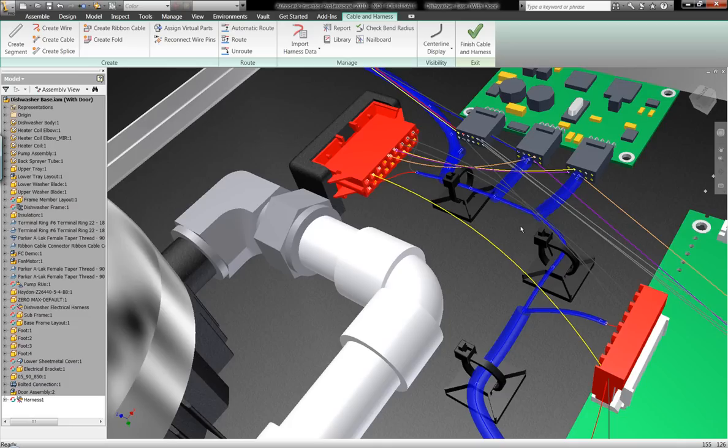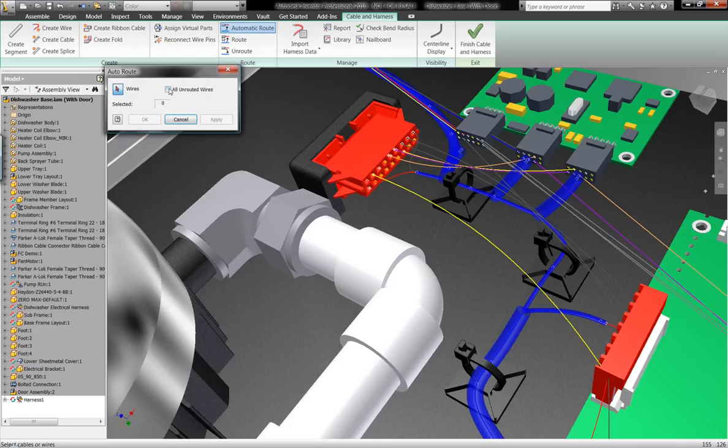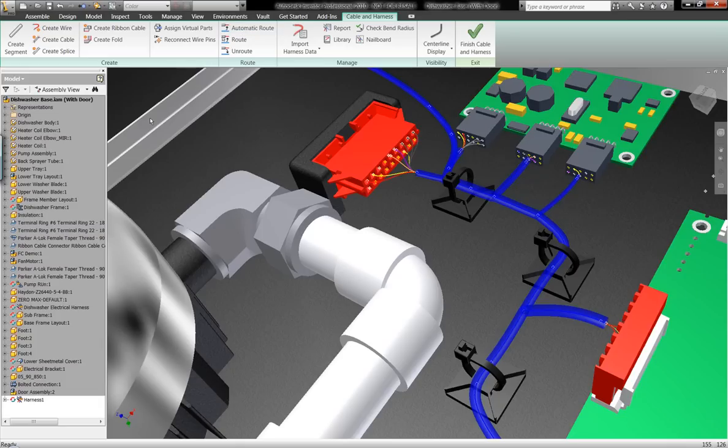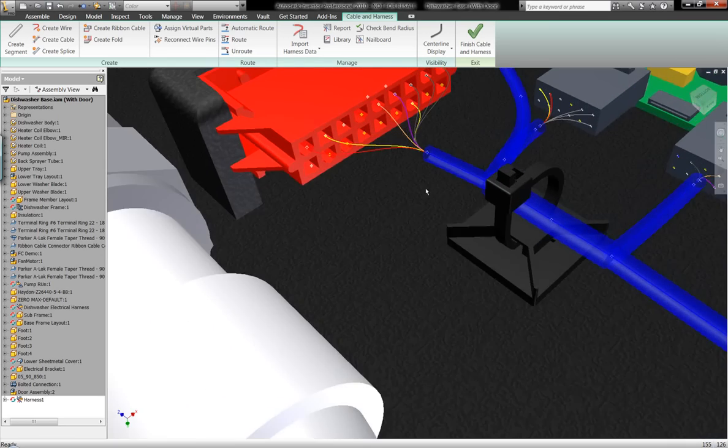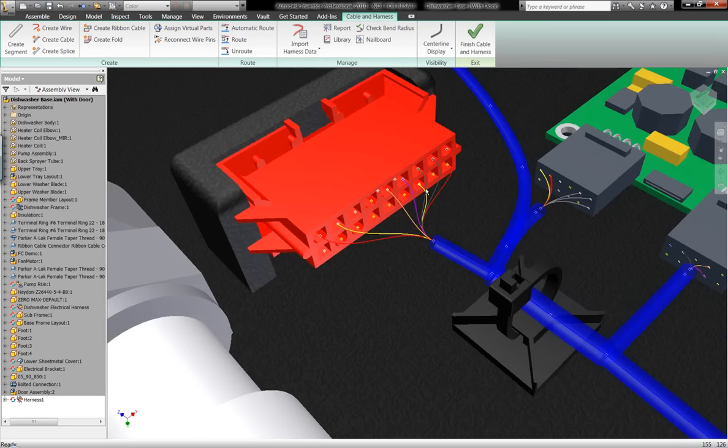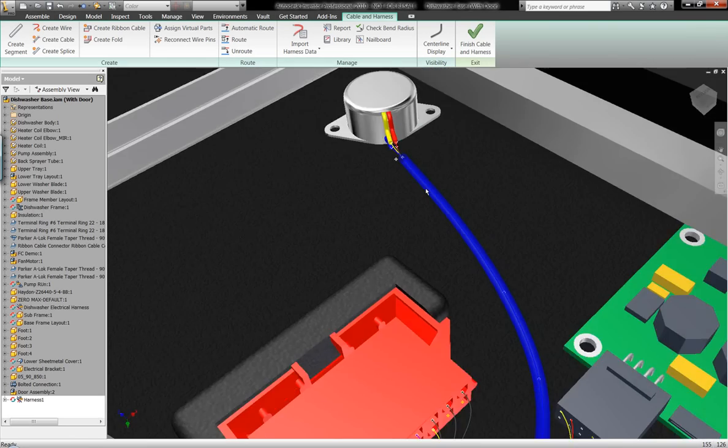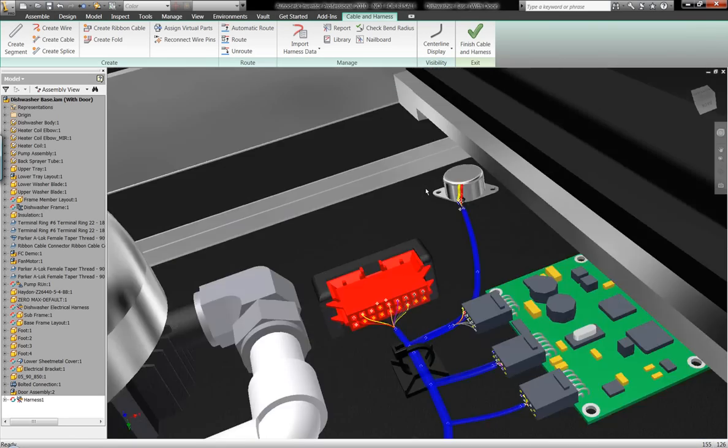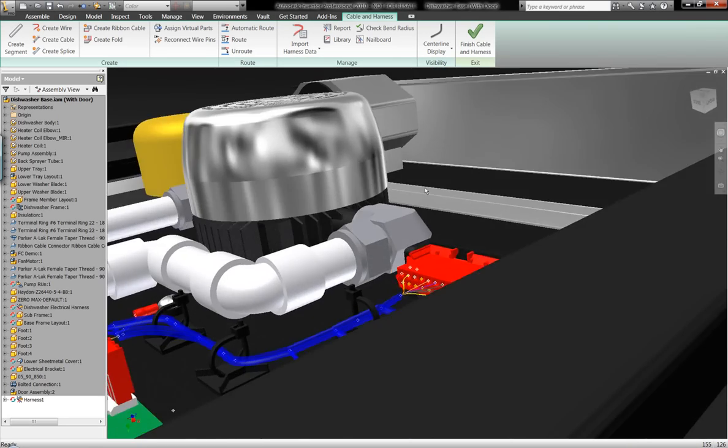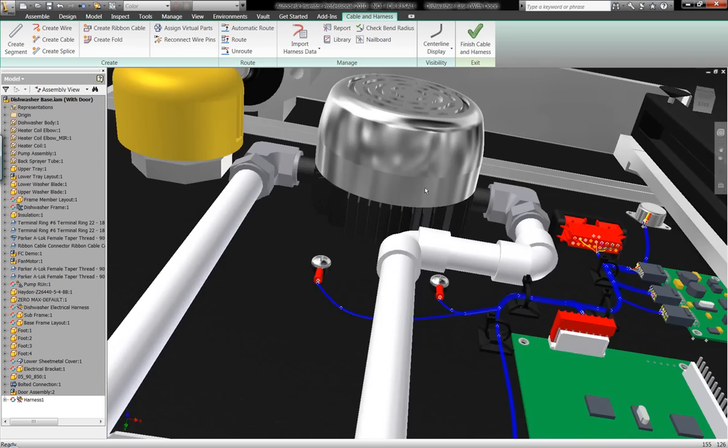As I add another wire, it's going to size that up. Now I can automatically route all unrouted wires. I don't have to do this one by one. Notice it's going to adjust the harness segment sizes based on the gauges of wires. The gauges were originally defined inside of AutoCAD Electrical.